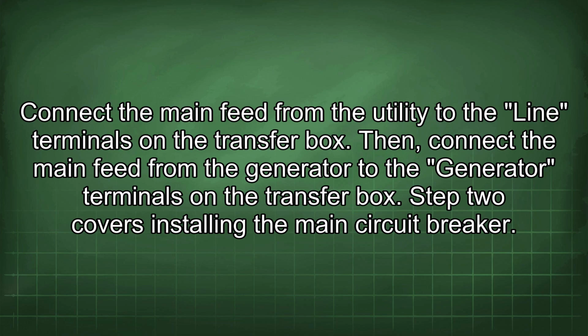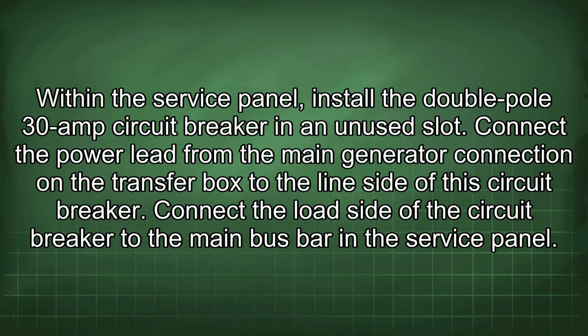Step 2 covers installing the main circuit breaker. Within the service panel, install the double-pole 30-amp circuit breaker in an unused slot. Connect the power lead from the main generator connection on the transfer box to the line side of this circuit breaker. Connect the load side of the circuit breaker to the main bus bar in the service panel.